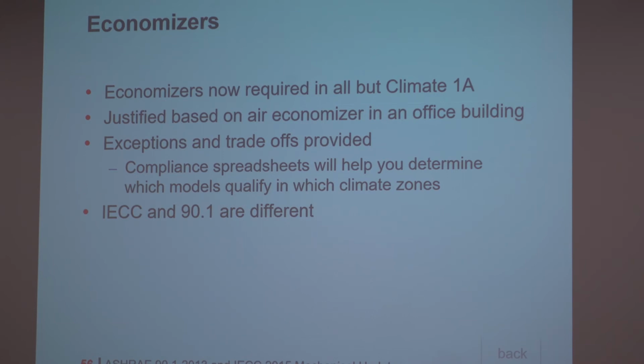Okay, so economizers is the biggest change that'll probably be coming up in your conversations with your HVAC contractors. It used to be that economizers were not required until you got to Climate Zone 5A. So 1A through 4A were exempt in the version of the code you're in now. Going forward, you're going to be required to have economizers. You can choose either air or water economizers. I will say that we justified the costs based on an office building application and an airside economizer. It's probably the rosiest application that we could have probably done, and if I had a time machine, I'd probably go back and do it differently.